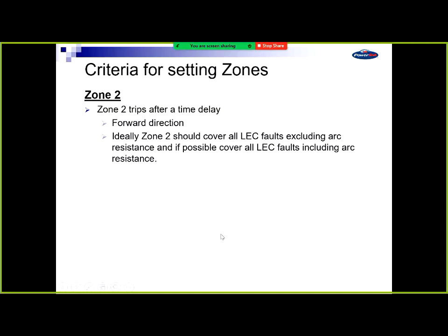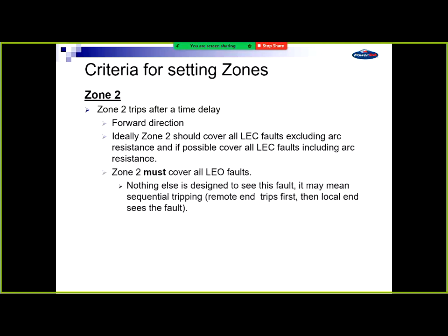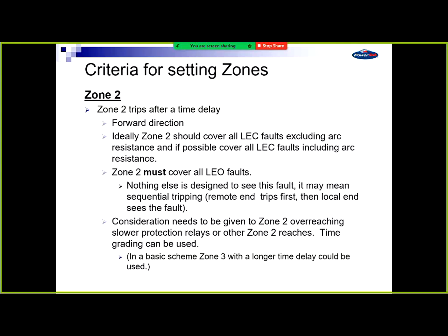Zone 2 is forward looking. We ideally want to cover all of our line end closed cases, including arc if possible, but sometimes including an arc impedance can get you very big reaches that are not realistic, and you can allow sequential tripping. If you've got a lot of arc resistance, your fault current's a bit lower as well. But the zone 2 must cover all line end open scenarios. Because if your breaker's open at the other end, nothing else is designed to see the fault on the feeder. The distance relay at my end here is designed, has to see the faults on all of it. None of the other protection in the network is designed to see faults on this feeder. So I must cover all line end open cases.